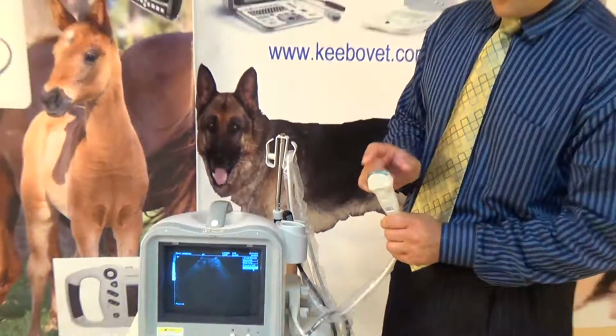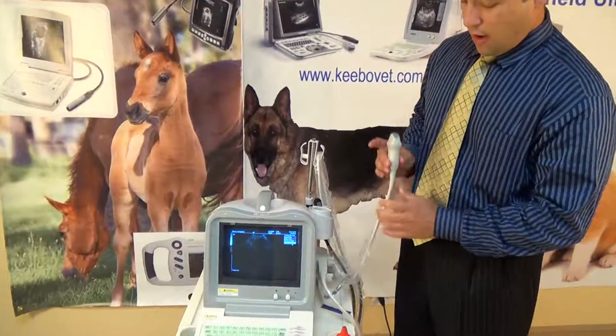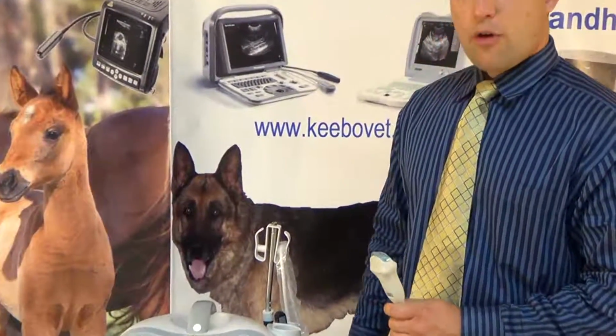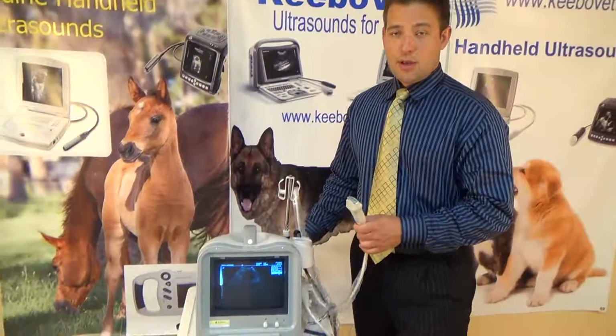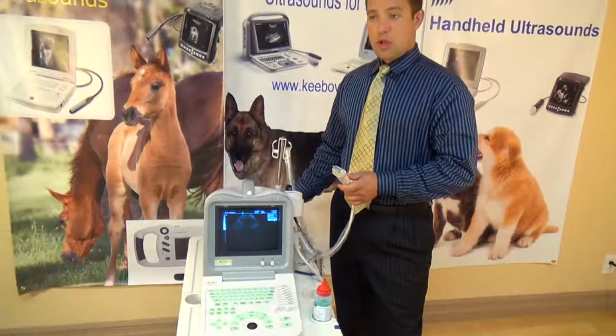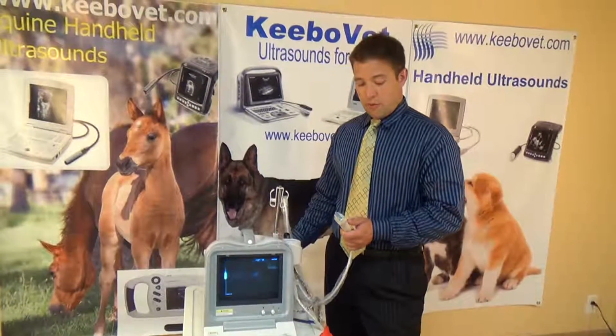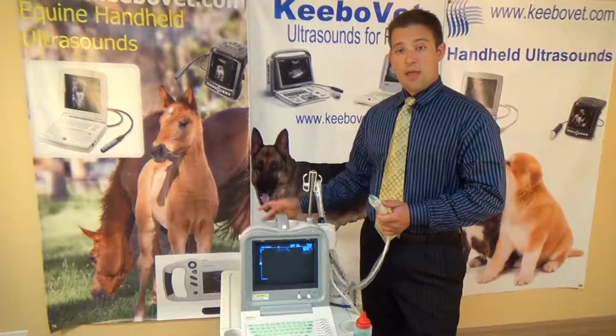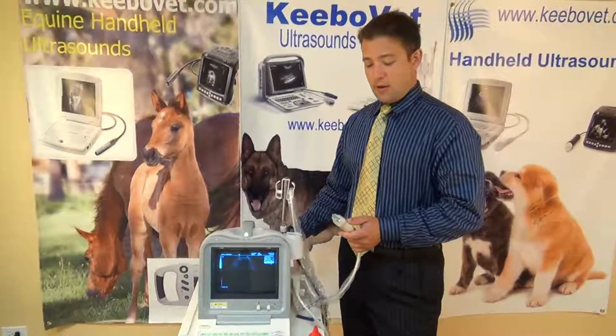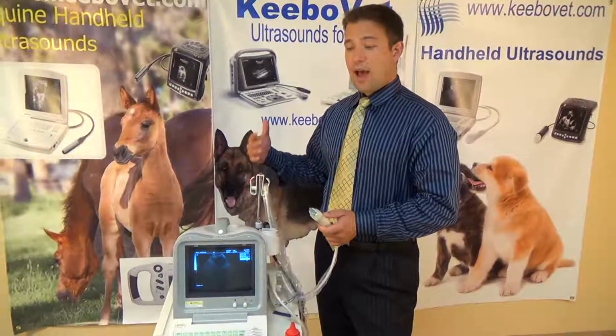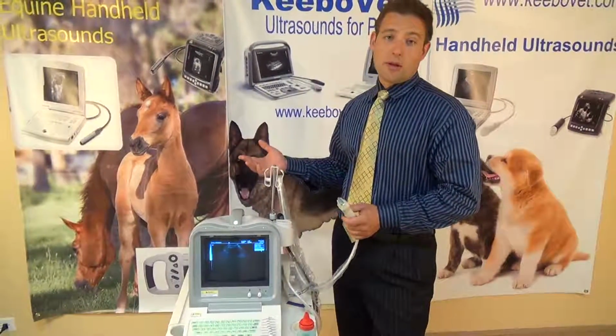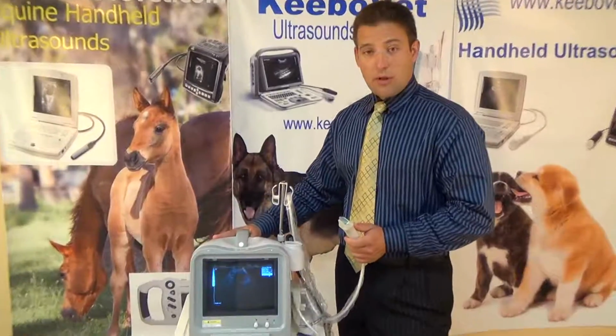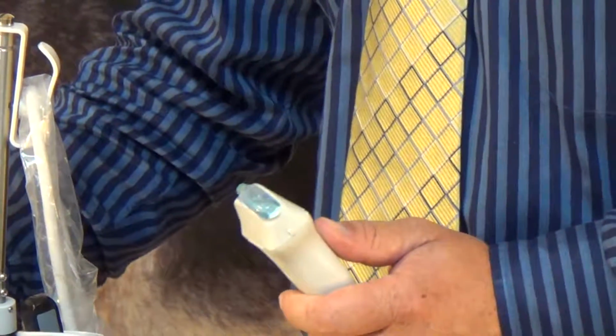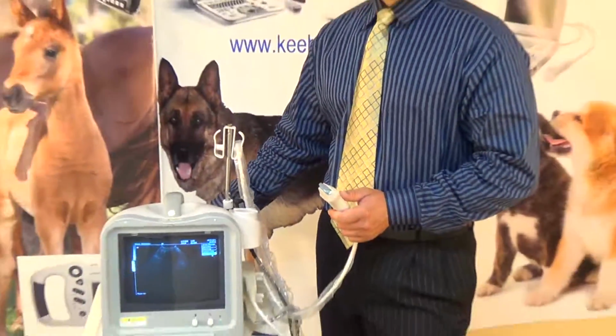So we have some gel here so you can at least see the image, but our probe has capability to go from 5 to 8.5 megahertz. Some of our competition usually only produces curved probes like this, or they provide you with them, that only go from 3 to 5 megahertz. And what that does is having a higher frequency allows for better quality, better resolution. So if you're doing smaller animals, this machine does not only large but small animals better than our competition's machines.